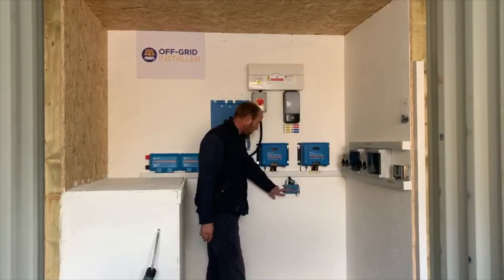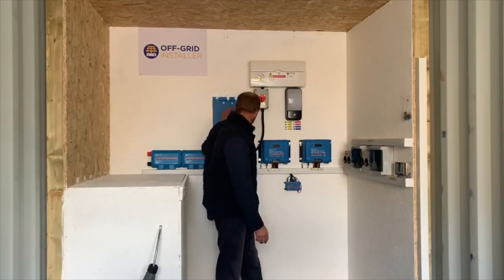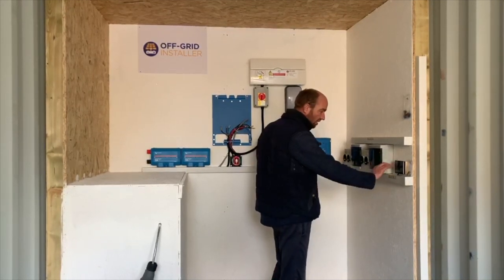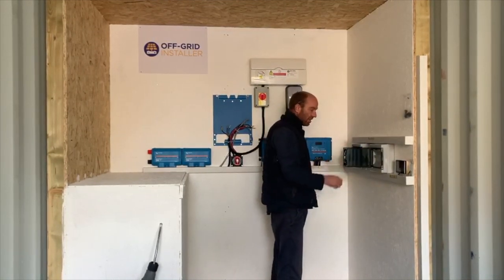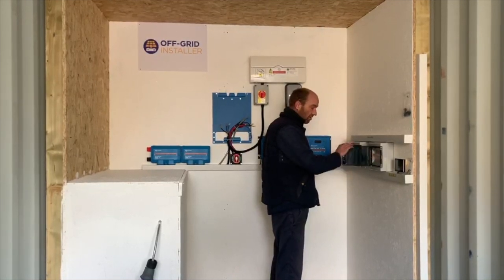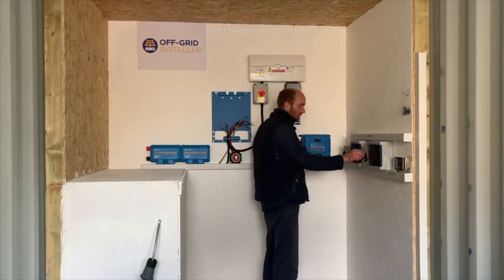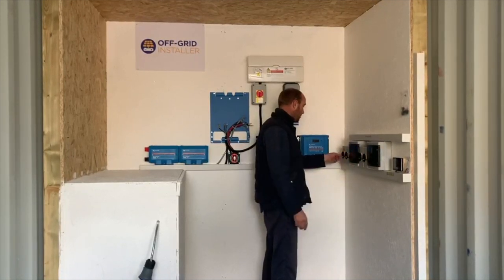This is the Cerbo - this is the brain of the unit. This communicates with all the relevant boxes on the wall. Here you've got the touch screen colour controller, where you can go in and change settings and see what the system is doing. These are string fuse boxes - we've got six string fuses for each array of 15 panels, so that's to control 15 panels, and that's to control the other 15. We've obviously got DC isolators for those 15, and DC isolators for the other 15.